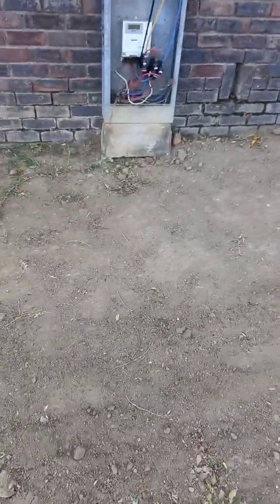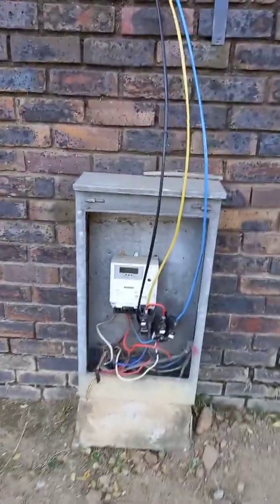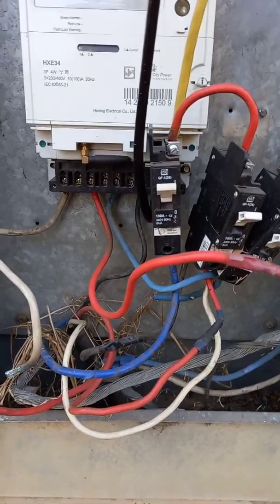In the meantime, there's the original house cable. It's a three-phase supply armoured cable — so the earth around the outside with the neutral and three lives inside. They've put a temporary feed from there with two phases to the meter box here.